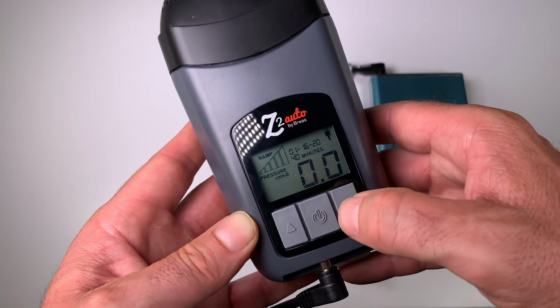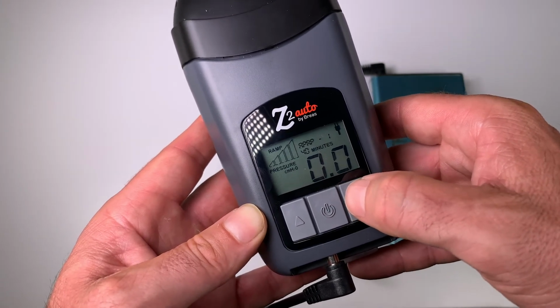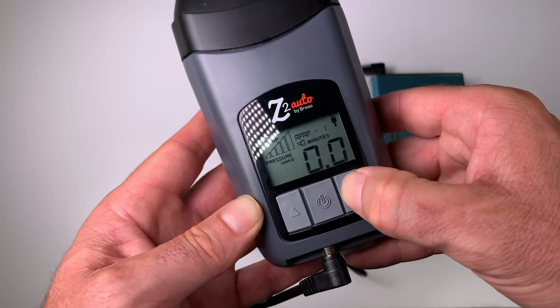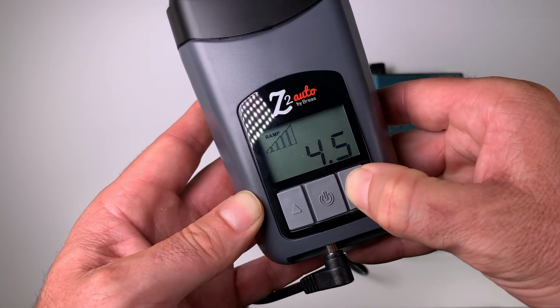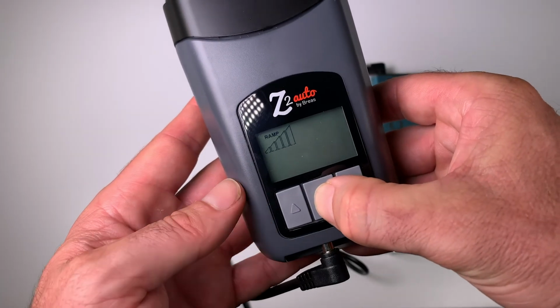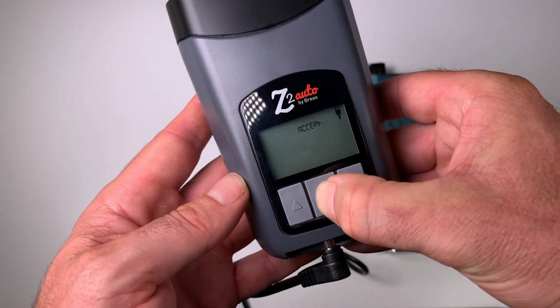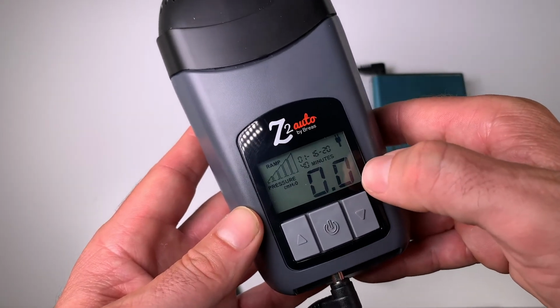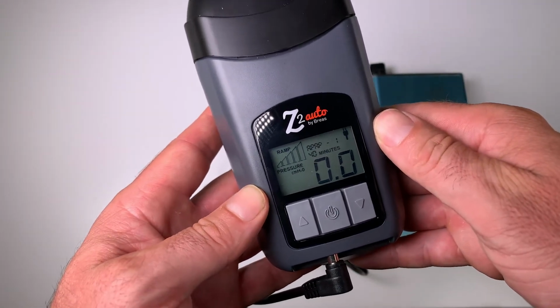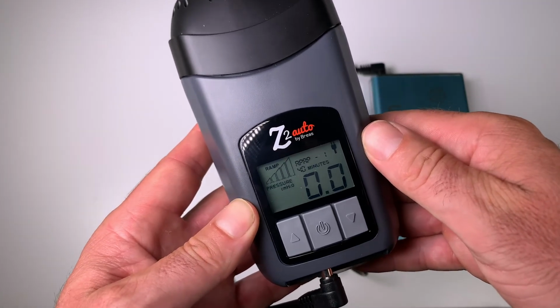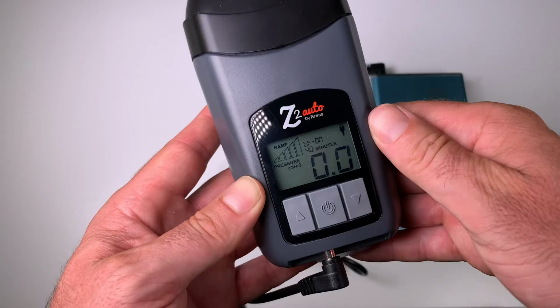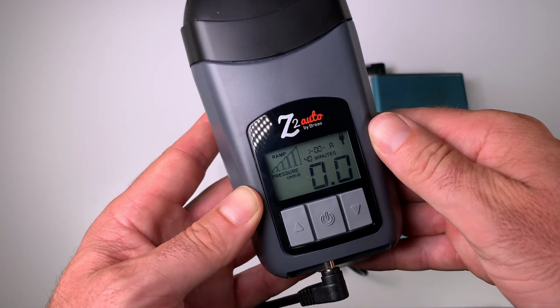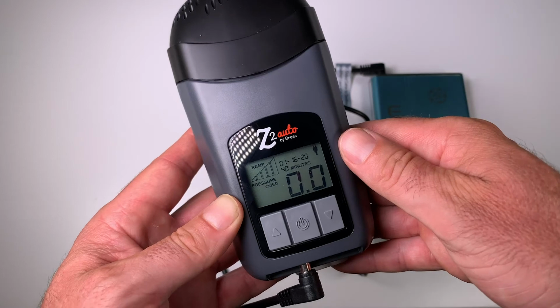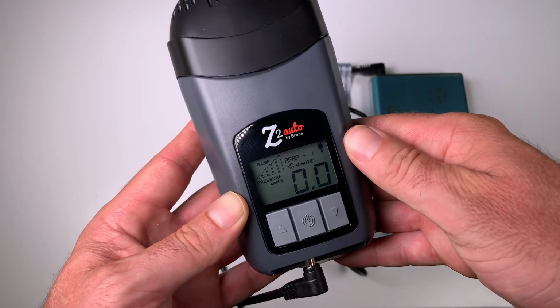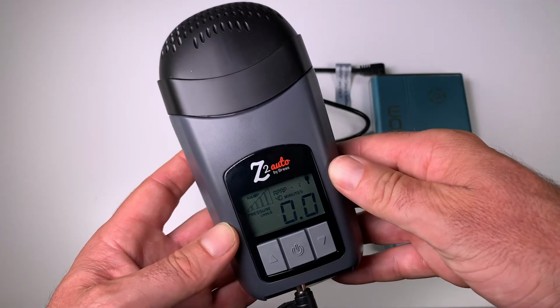But you can change that. You might have your minimum APAP at 6 and your ramp start pressure at 4. And you might change the ramp time to 20 minutes. Okay, and that means that over 20 minutes, the pressure is going to go from 4 to 6. And then once that 20 minutes is up, the auto algorithm is going to kick in and it's going to automatically adjust the pressure between 6 and whatever you've set your auto high level to, which might be 12, 14. You could leave it at 20 if you want. And the machine will automatically adjust that pressure for you minute by minute. It's going to sample your breathing and adjust. So it gives you perfectly tailored therapy every minute of every night, which is the beauty of an automatic machine.